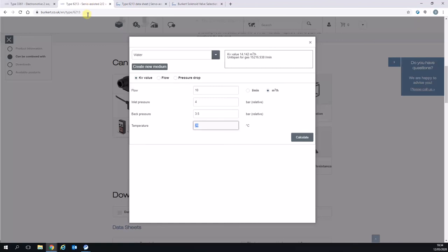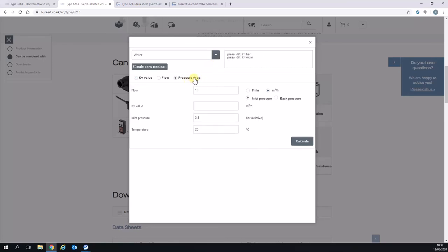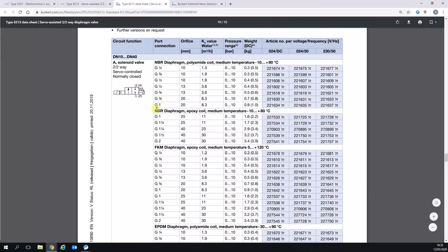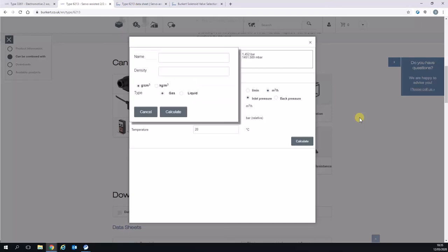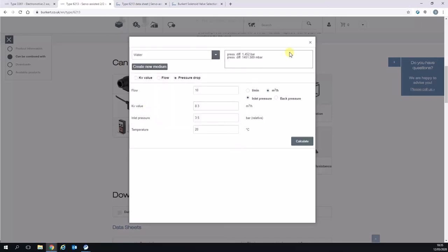I'll also show how we can use this to calculate the pressure drop. This is the most common thing we generally use this calculator for. What I'll do is I'll actually use the one inch DN 20 we've got here with a KV of 8.3. So we've got 10 meters cubed per hour at a KV of 8.3.